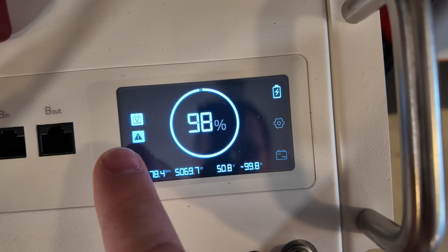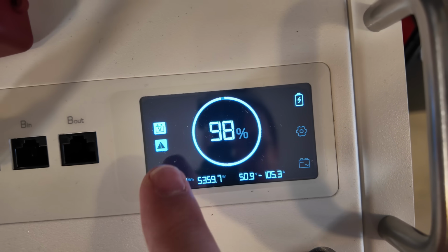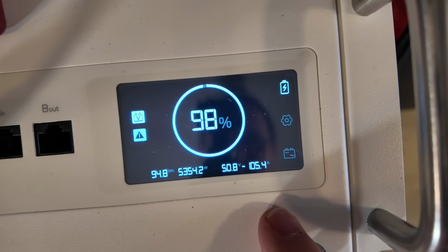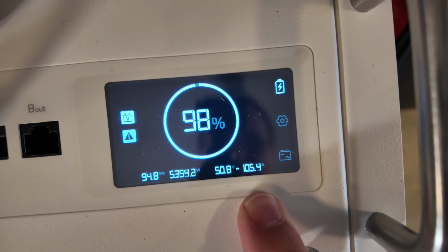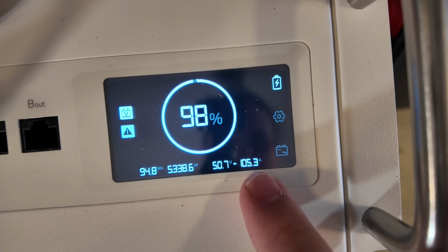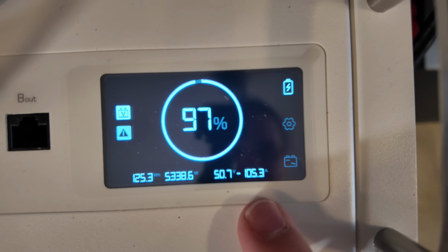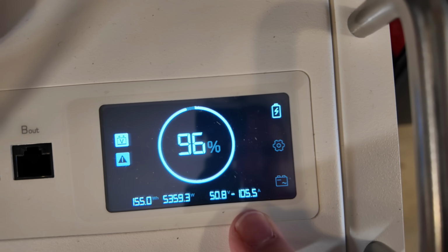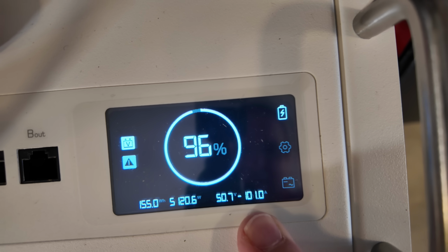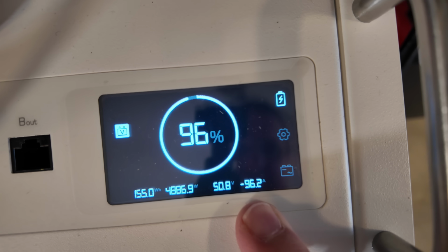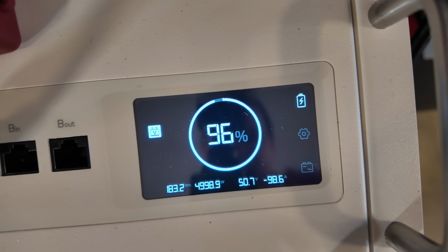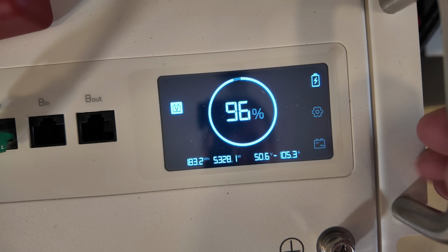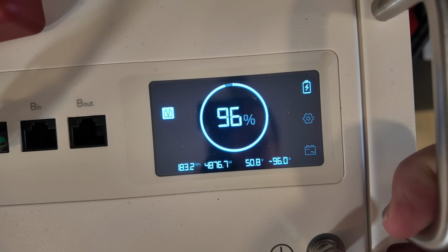We still have the notice though, of an overcurrent event happening. So this will probably run for a couple of minutes before it shuts down fully, just because we're barely over the limit. Still holding steady. Now we're fluctuating between 105 and the mid-90s because that heat gun is fluctuating a little bit. Can this support generally a continuous 100 amp load? Yes.